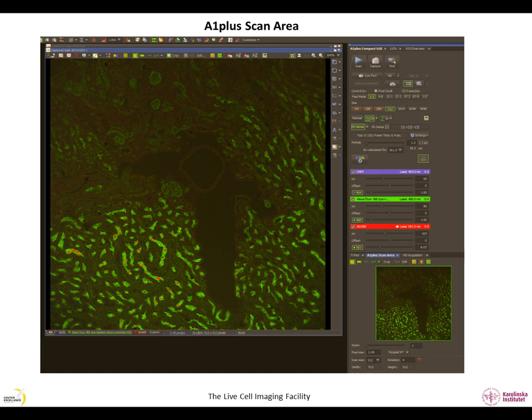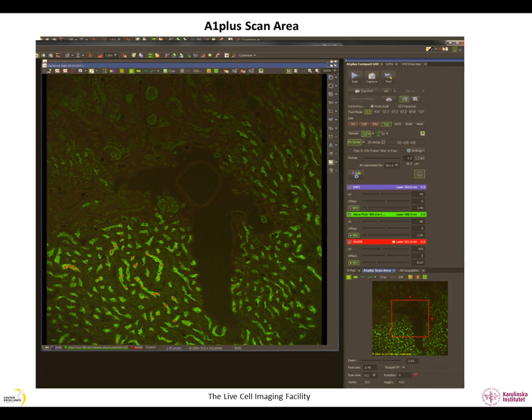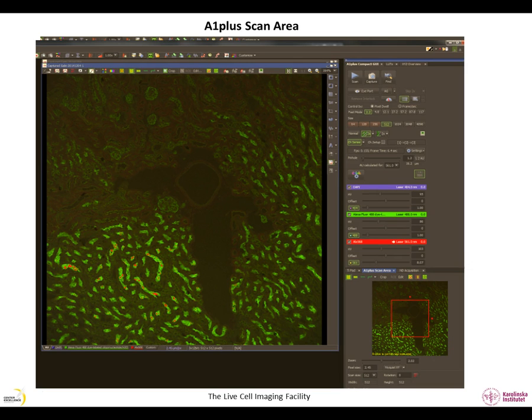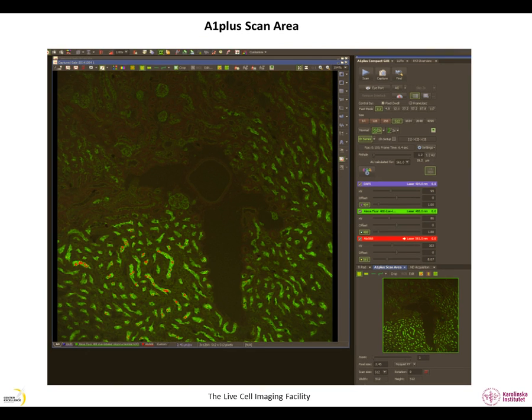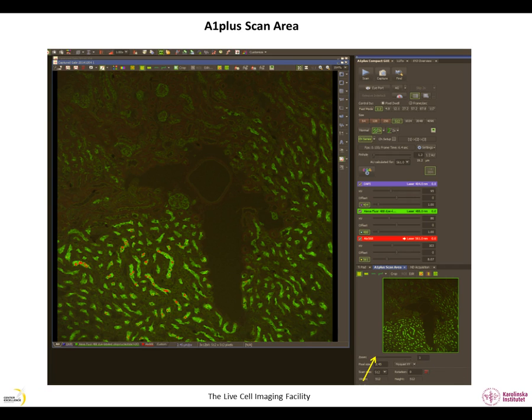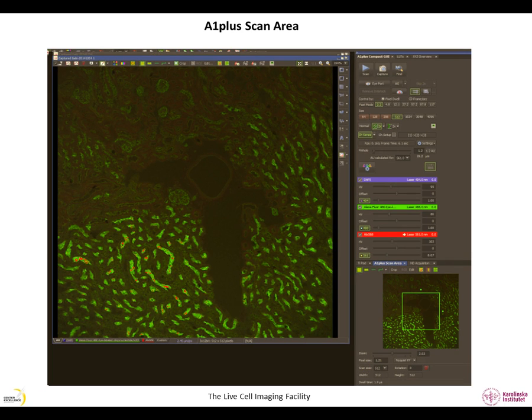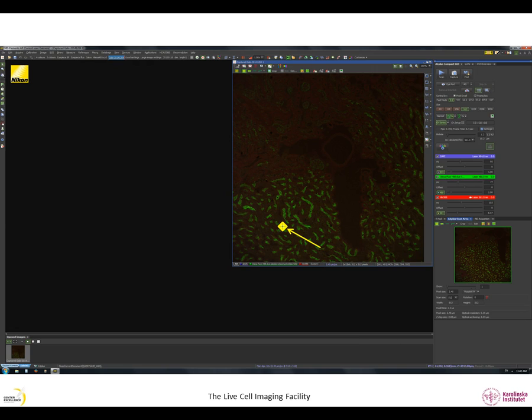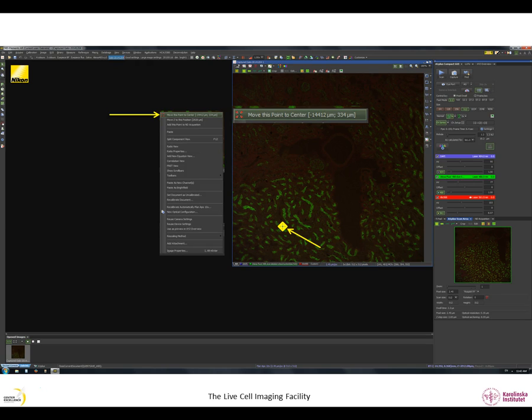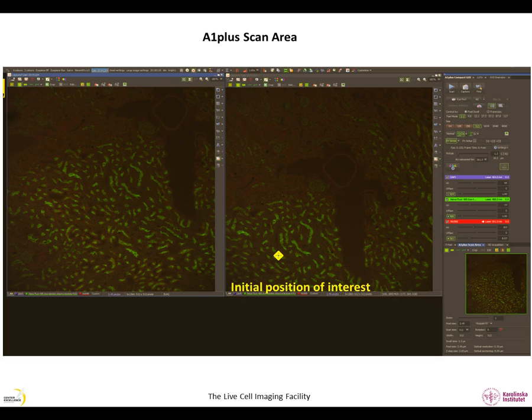Now you have grabbed an image. Let's assume that you would like to zoom more. You can do that in two ways. Resize the green square. The square becomes red and you confirm the new scan area by either clicking on the square or by hitting enter. You can also enter the zoom value of choice here or move the slider and hit enter. You can also use an image to physically move the stage. Let's say that you would like to grab an image with this point at the center. Place your mouse at the point of interest. Right click and select move this point to the center. This moves the stage. You can now grab an image with your position of interest in the center of the image.